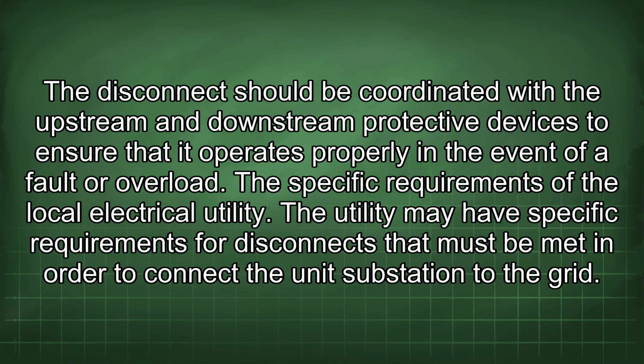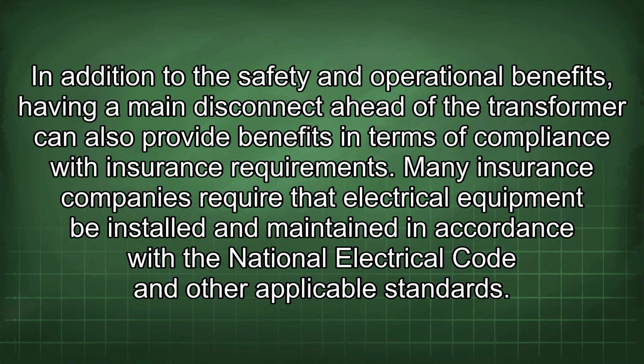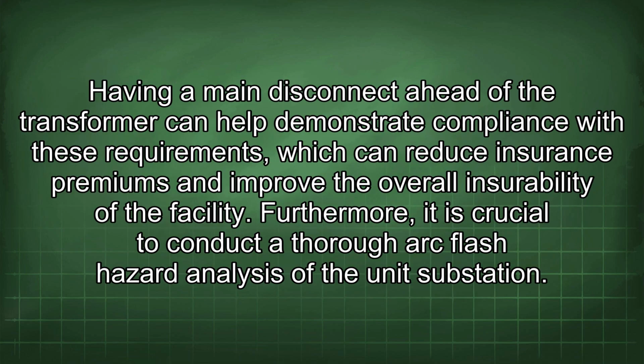The specific requirements of the local electrical utility. The utility may have specific requirements for disconnects that must be met in order to connect the unit substation to the grid. In addition to the safety and operational benefits, having a main disconnect ahead of the transformer can also provide benefits in terms of compliance with insurance requirements. Many insurance companies require that electrical equipment be installed and maintained in accordance with the National Electrical Code and other applicable standards. Having a main disconnect ahead of the transformer can help demonstrate compliance with these requirements, which can reduce insurance premiums and improve the overall insurability of the facility.